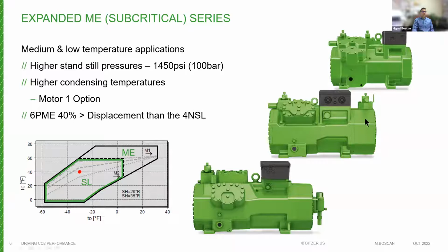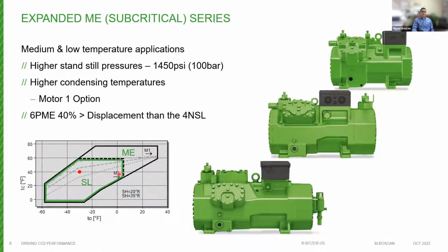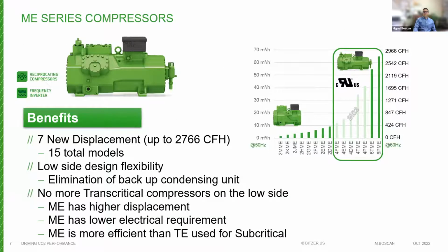In the bottom corner here, you can see the increased window of the ME compressor up here versus the smaller window of the SL compressor. So the ME series provides system designers flexibility on the low side of a CO2 system. The most significant benefits include the larger displacement options. The largest ME compressor is 40% larger than the largest SL compressor. Also, for systems that require lower or higher low side standstill pressure, the ME series provides an optimized, higher efficiency compressor for this application, and eliminates the need to use higher horsepower transcritical compressors. The largest ME compressor is the 6PME, and it has about 70% more displacement than the equivalent TE series.